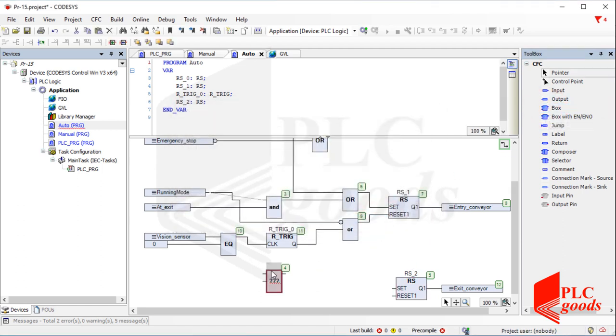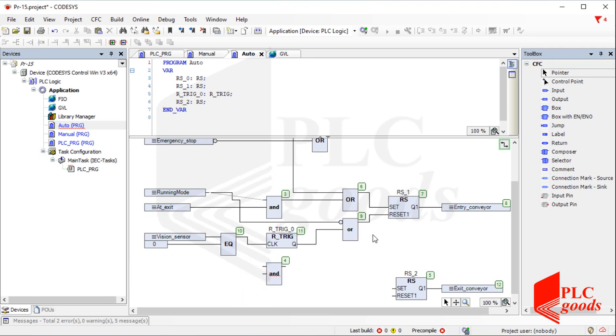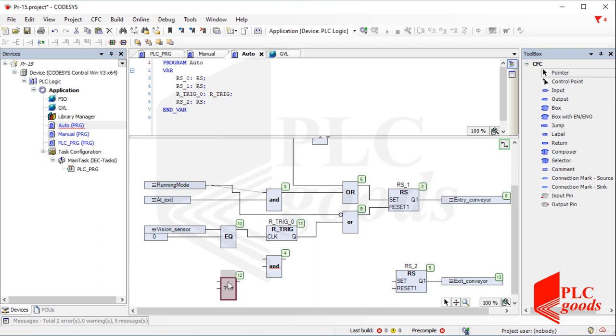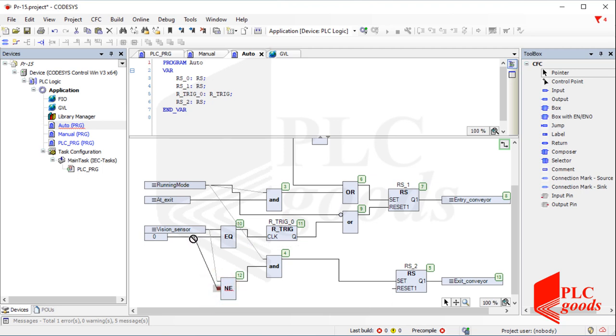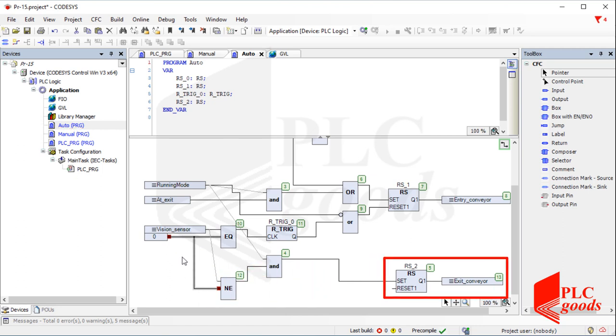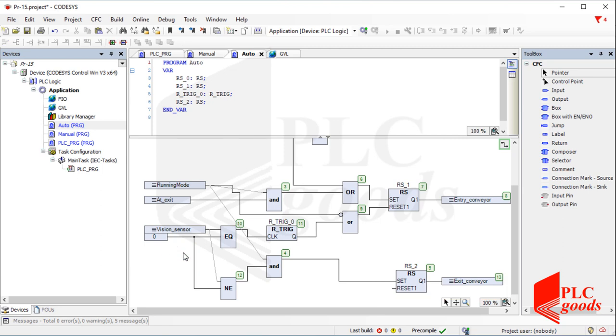Now I'm going to determine the only condition that can turn on the exit conveyor. The initial condition to turn on the exit conveyor is that the running mode is enabled. After that, if the vision sensor detects a new product below itself, the exit conveyor must be enabled. Briefly, if the vision sensor is not equal to zero, it means a new product is below the vision sensor and must be moved by the exit conveyor. Note that inputs can be repeated if there are lots of branches that make the program seem complex. For example, instead of using two branches, let me repeat these two inputs.